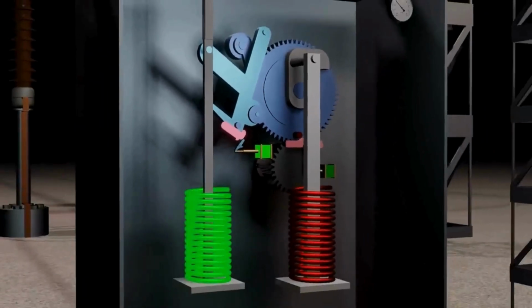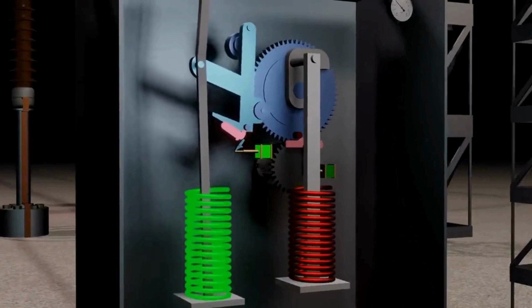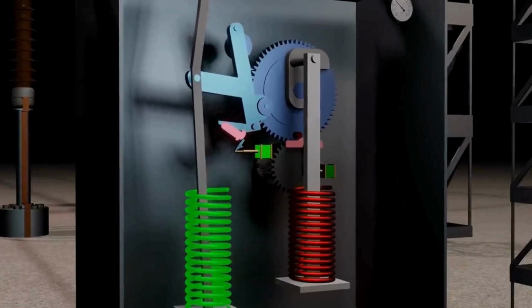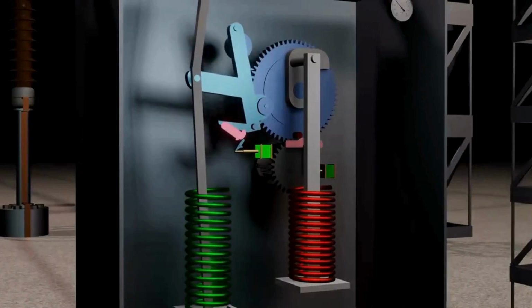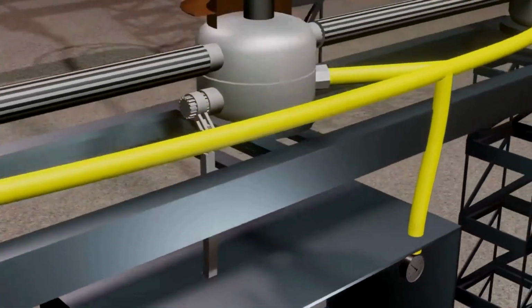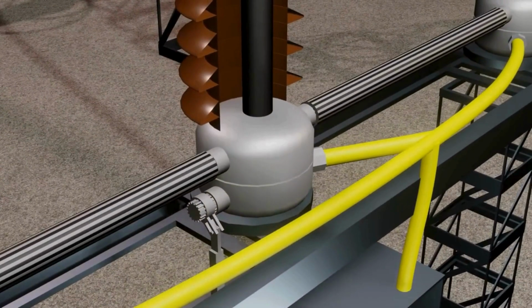Now back to the point. So the high current of the fault will flow through the relay, then the relay will operate. And the plunger in it will apply force to the outside. Due to which the holding latch here will free the lever, and the force of the spring loaded on the lever comes in. Then the spring will pull this rod downwards at a very high speed and the line will be opened. But it is not that easy.